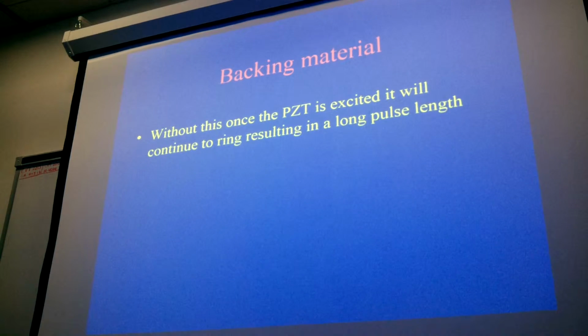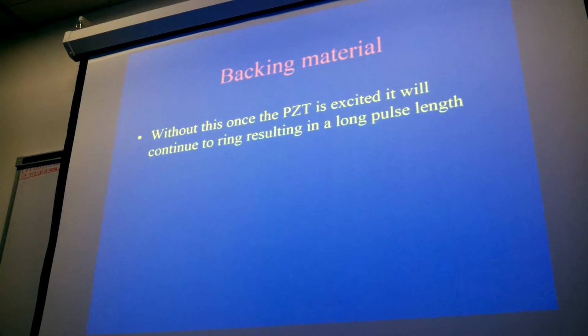One, it stops the ringing. The second one is made up of a type of material that stops the transmission of sound from going back and forth. You will, later on when we get into artifacts, hear a term called reverberation, where it's bouncing back and forth between these two things. And that's what the backing material also does. It stops the reverberation from the back side of the transducer crystal. Otherwise, you get more artifacts in it. You don't like artifacts, do we? No. We only want to create things that are real, not things that are fake.